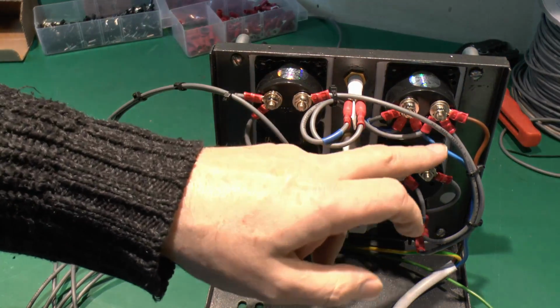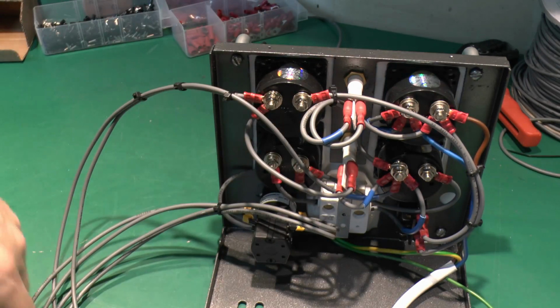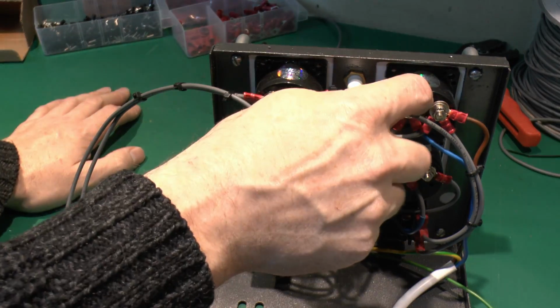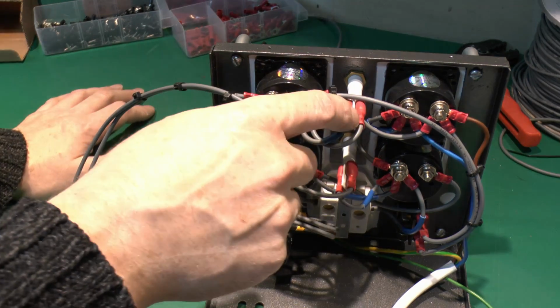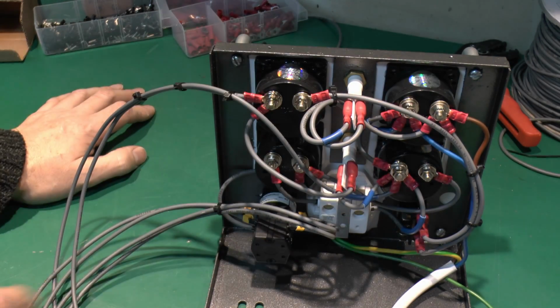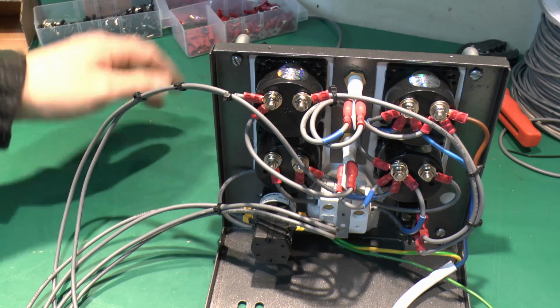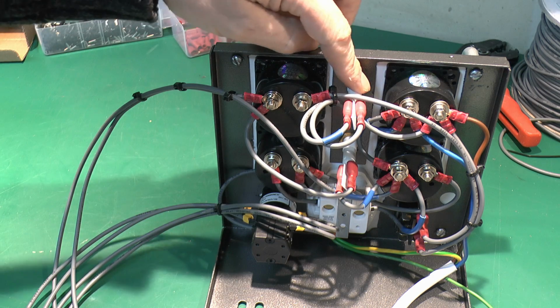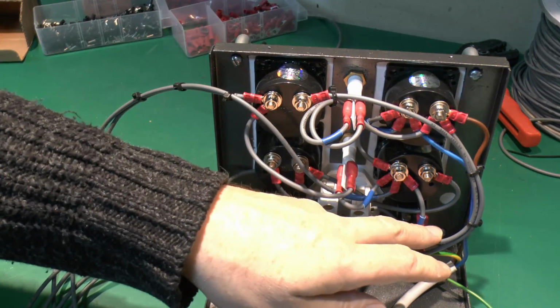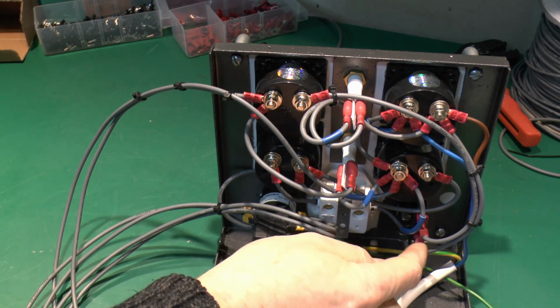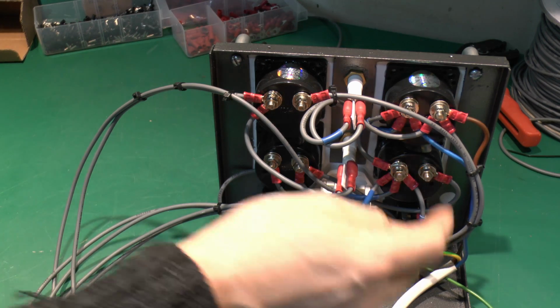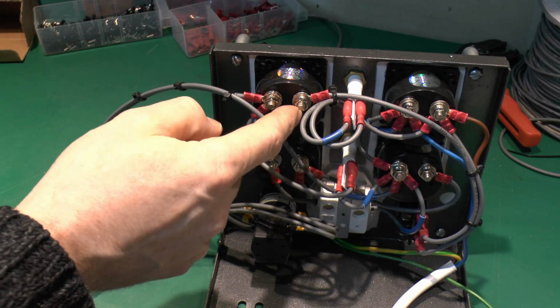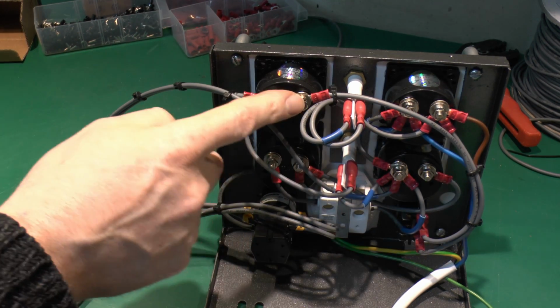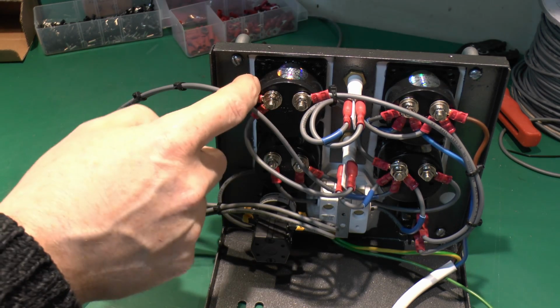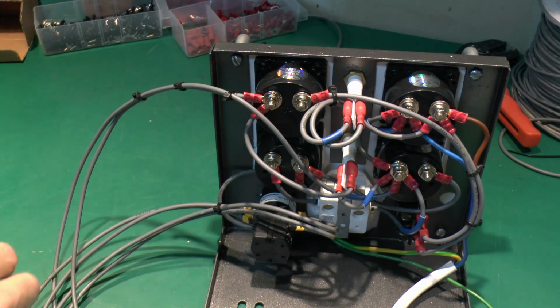Then we have various other lines going off to two other areas there, and the neutral also comes in onto this meter as well. This top neon is wired to these also, so basically when you plug it in, power is applied, this meter will show the voltage, and this indicator will illuminate regardless of the position of the switch. With the switch off, that's pretty much all that happens, but when this switch is on, power comes down to the switch and then back over here, powering things over here, and this will go through the amp meter here, going straight through.